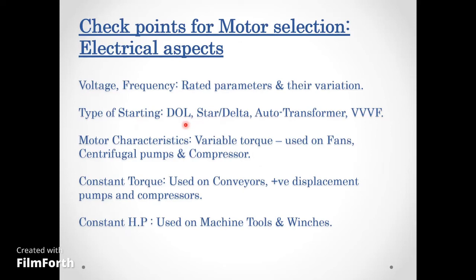Motor torque characteristics are another checkpoint. Variable torque is used for fans, centrifugal pumps, and compressors. Constant torque is used for conveyors and positive displacement pumps and compressors. Constant horsepower (power) is used for machine tools and winches. The required torque type depends on the application.